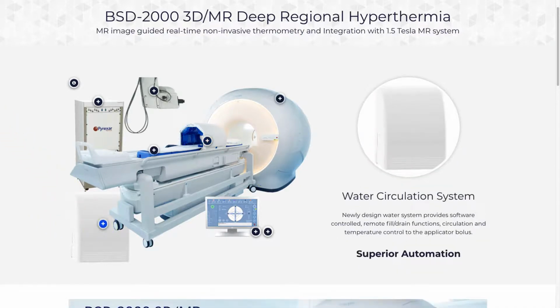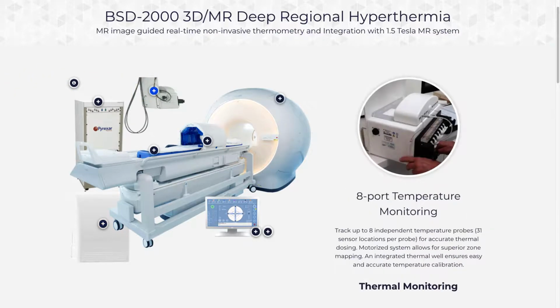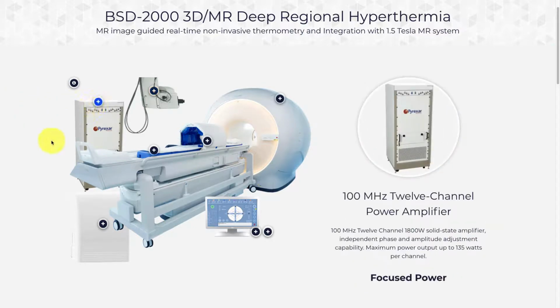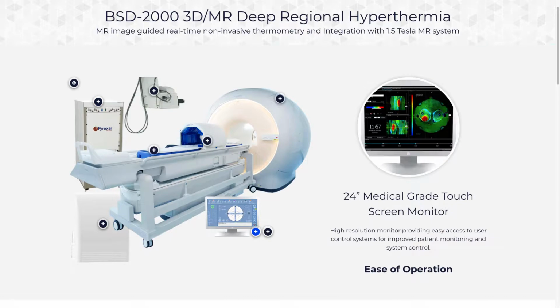Our newly designed water system provides software-controlled remote fill and drain functions, circulation, and temperature control to the applicator bolus. An 8-probe thermal mapping system is provided as backup. The 100 MHz 12-channel 1800-watt solid-state amplifier offers independent phase and amplitude adjustments. The maximum power output is up to 135 watts per channel. And the computer control system is housed in a 24-inch medical-grade touchscreen all-in-one PC with embedded Windows operating system.